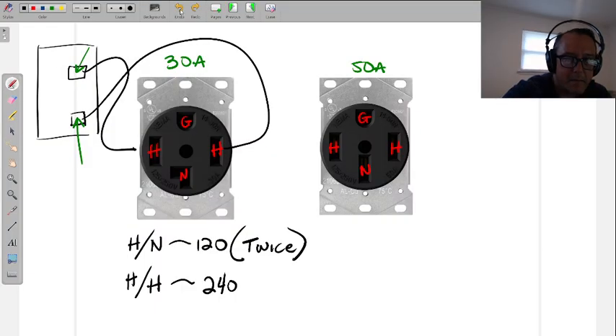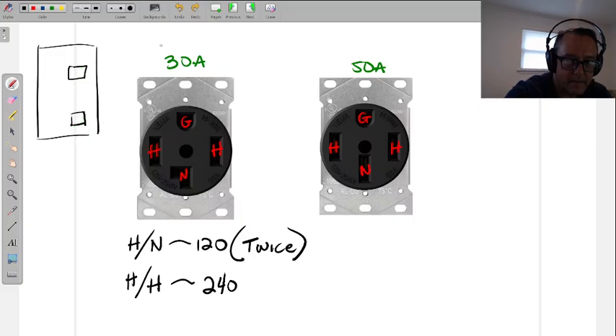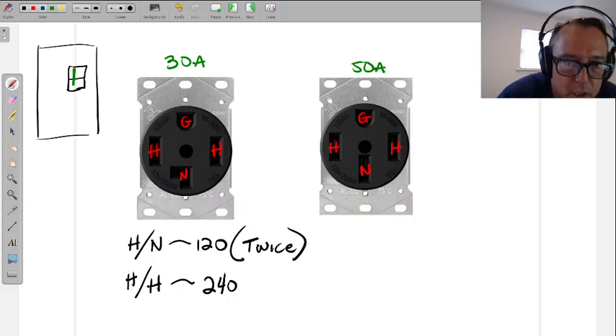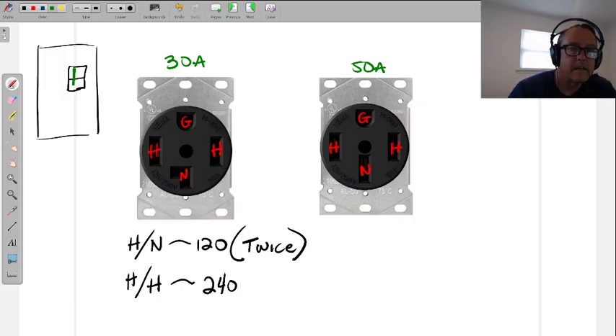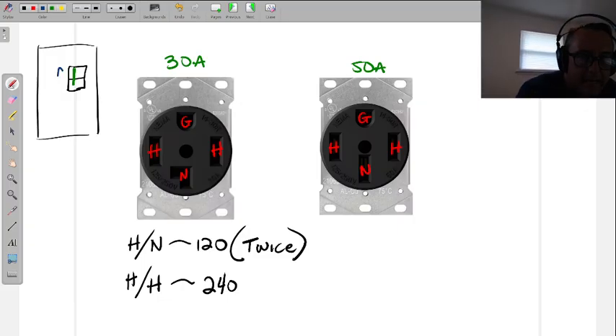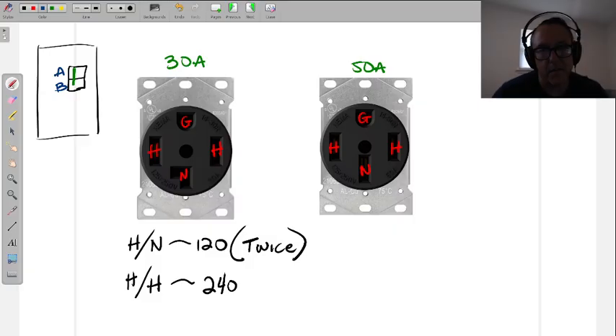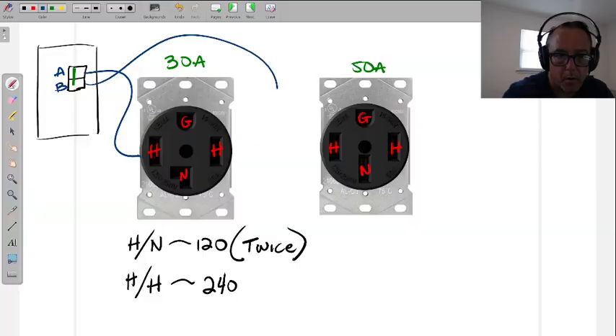Now, it's already a bad idea to separate these in two different locations. The code says both of these have to trip at the same time. Not that you can't use two singles, just that the two singles would have to be side by side. You can set this up with a pin that connects two breakers together, or with a solid number 12 wire. The main thing is you avoid not picking up the second phase, which is the important part.